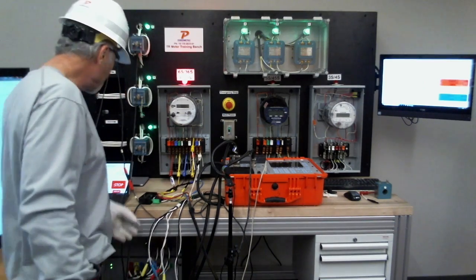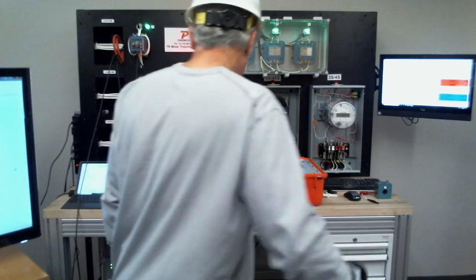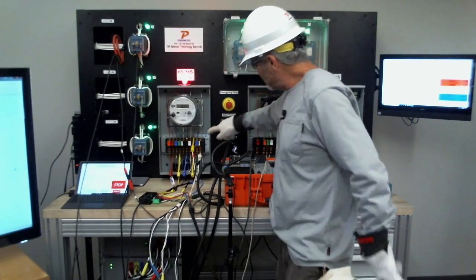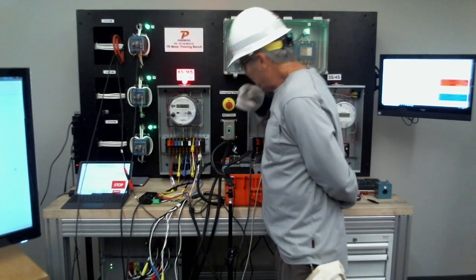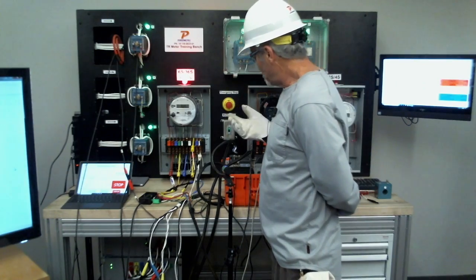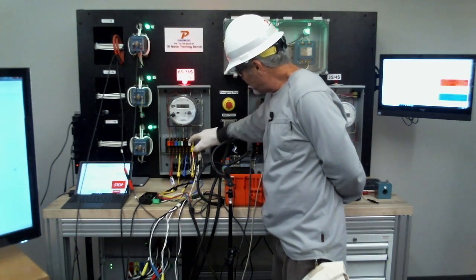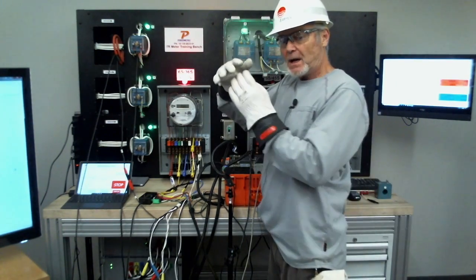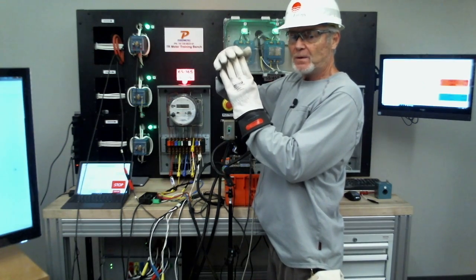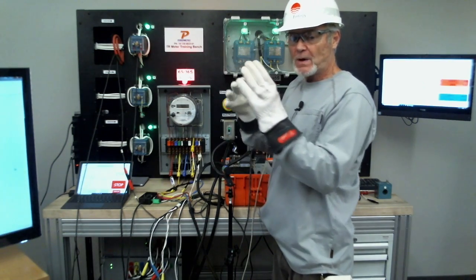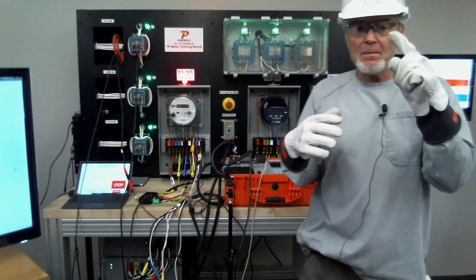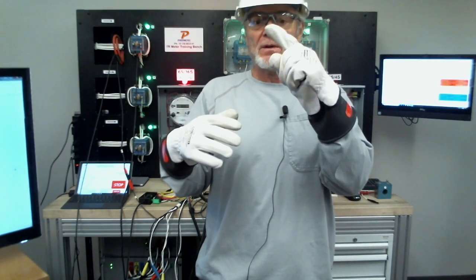So the A phase is for driving, B phase is over here to read with. What I do is, you can use alligator clips, but I like these easy hooks because the weight of that cable when you're out in the field can sometimes pull down. Remember we talked about this, that tab on that test switch is angled upward.